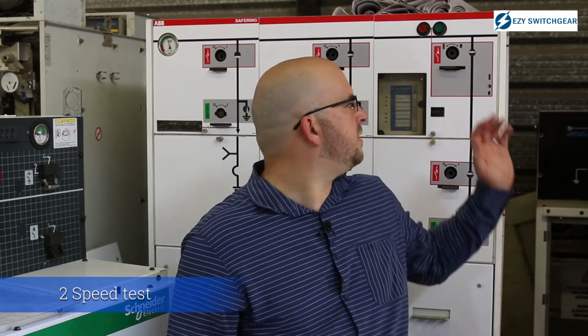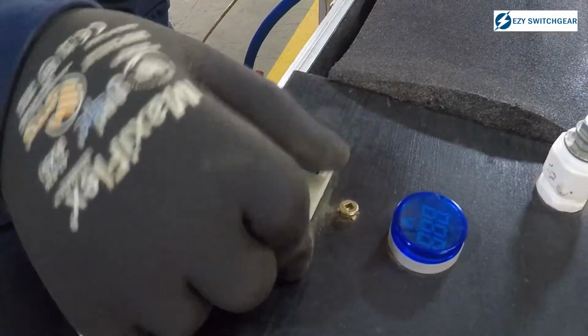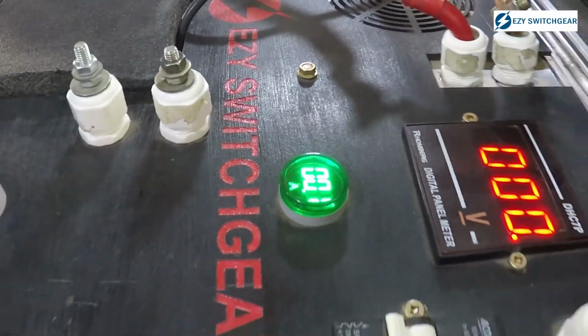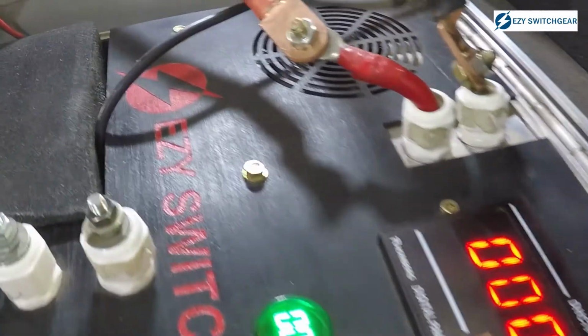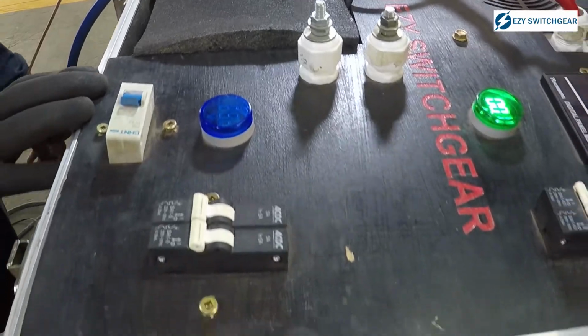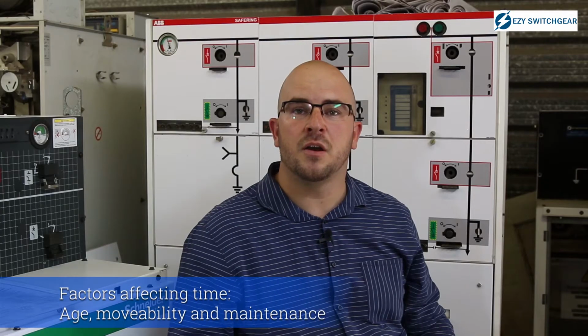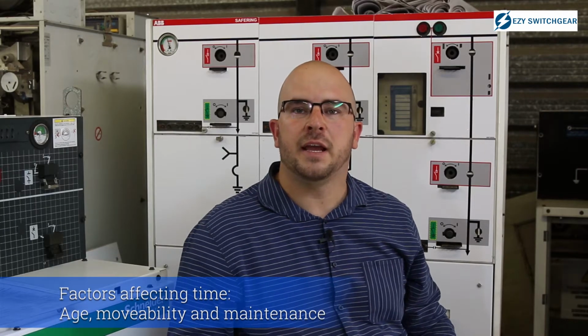And then the second one is the speed test. Whenever there is a fault on the system, you want these switchgear to switch as fast as possible, isolating the fault as soon as the protection settings tell it to trip. If the mechanism is old, stuck, or not maintained properly, it can take a longer time to trip and therefore put at risk the whole network.